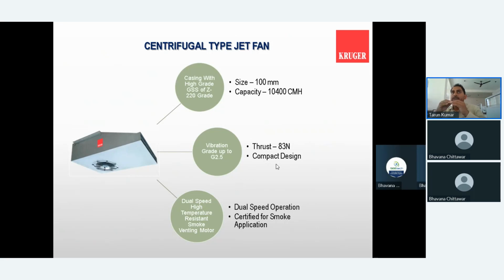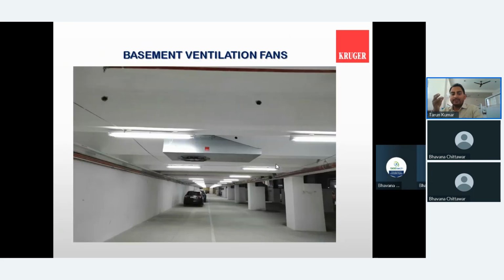So commercially, if you see the installation cost, the cable cost, the cable tray cost, everything comes down from a costing point of view, and it becomes more effective than the axial jet fan. But the purpose is the same, basement ventilation. Here you can see the site photograph of the installation, and the other feature you can see is that it is very low in height.